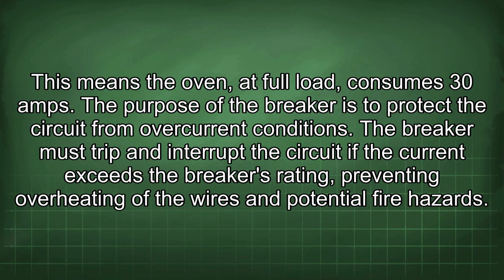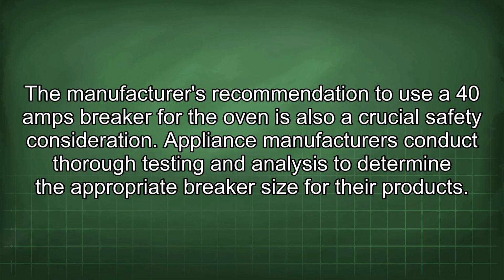The purpose of the breaker is to protect the circuit from overcurrent conditions. The breaker must trip and interrupt the circuit if the current exceeds the breaker's rating, preventing overheating of the wires and potential fire hazards. The manufacturer's recommendation to use a 40 amps breaker for the oven is also a crucial safety consideration. Appliance manufacturers conduct thorough testing and analysis to determine the appropriate breaker size for their products.